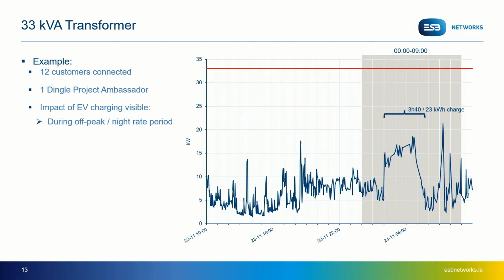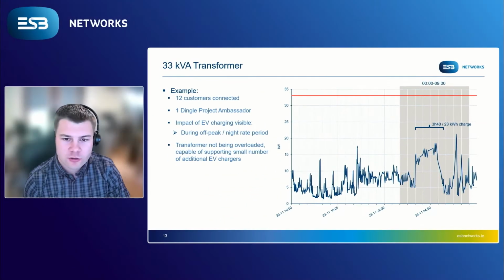That said, we can still see an increase in demand for around 3.5 hours during the nighttime period, and in this case the charge was shorter and didn't last as long into the night. During the 24-hour period, there's some way to go before this transformer will be overloaded, and it's likely capable of supporting a small number of additional chargers before any issues arise. This also shows that shorter, more frequent charges may be better accommodated by the network, and provide more flexibility in terms of when charging could be completed during that nighttime period.